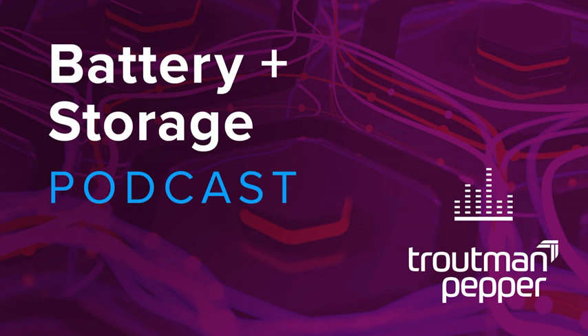I'll first talk about a small scale example, then bring it up to utility scale. When you turn on a diesel generator, there's usually two red top batteries — that's the slang term. It's 24 volts of battery, and this is what gets the generator spinning so it can start to produce power and consume diesel. To get that generator going, you have to have energy, you have to have power, and that's what the batteries are doing.